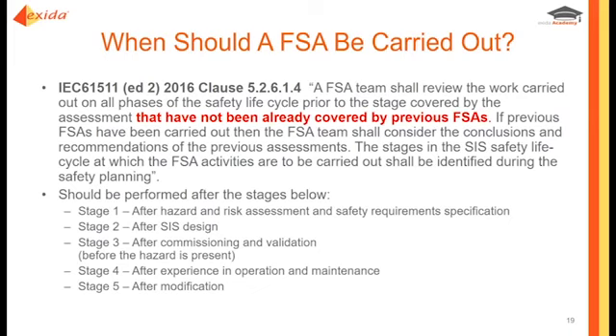Well, it means if you're going to be doing your first FSA as FSA 3, which is one of the mandatory FSAs you need to do, then you have to make sure as part of FSA 3 you cover FSA 1 and 2 if they were not done before. So this is very important, because if you see FSA 3, stage 3 is after commissioning and validation prior to startup. So if that's the place where you do the first functional safety assessment, you are running significant risk, because if there are problems, you cannot start up. And therefore, fixing the problems becomes far more expensive and, of course, can result in costly delays.